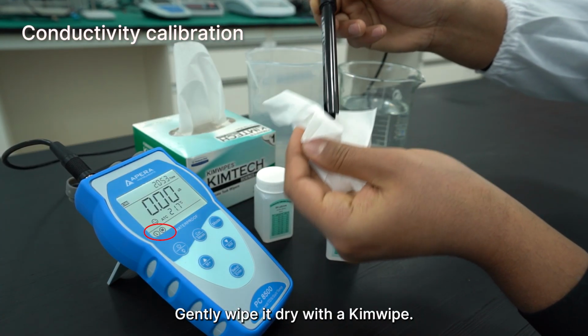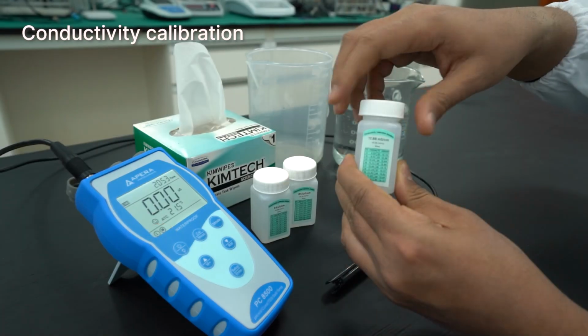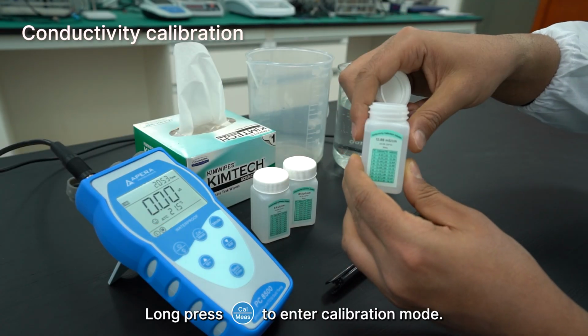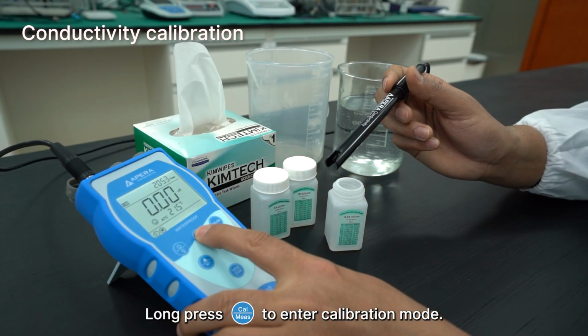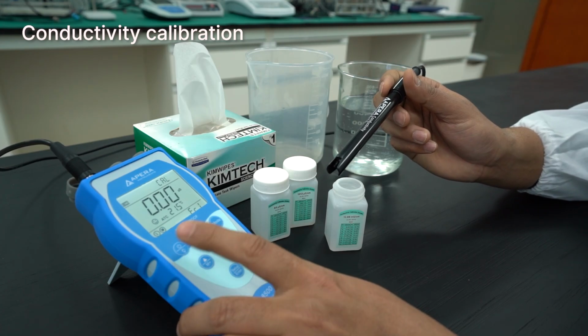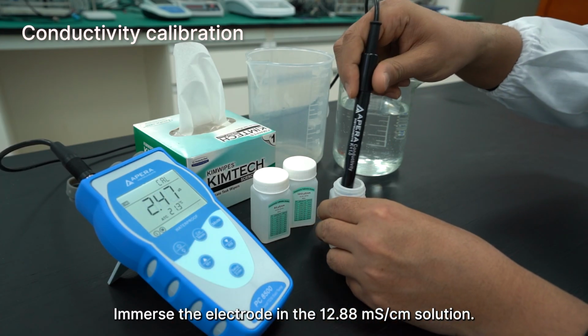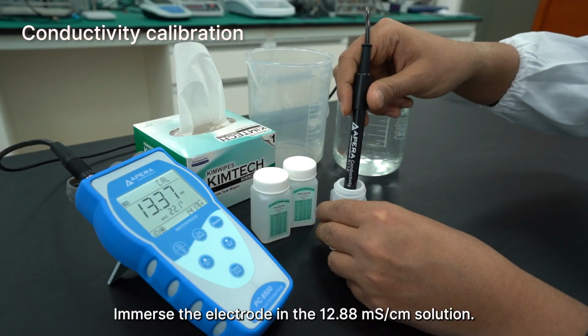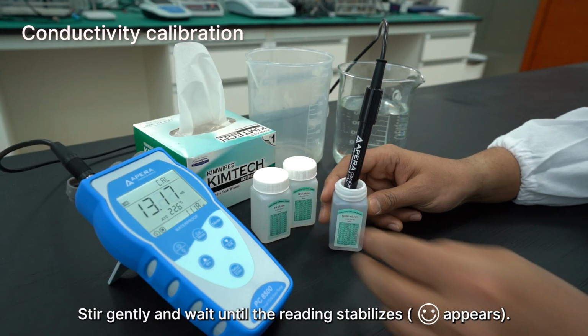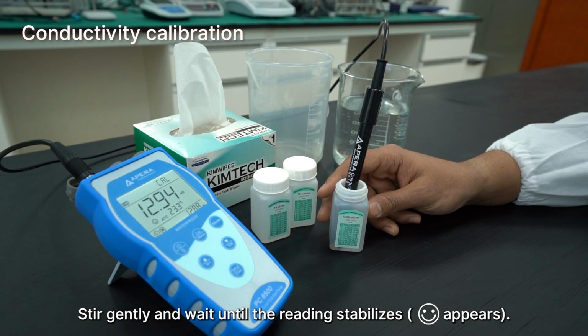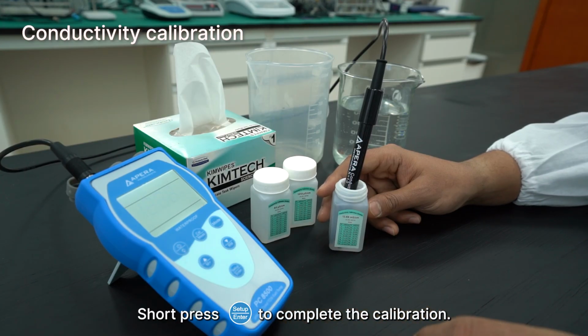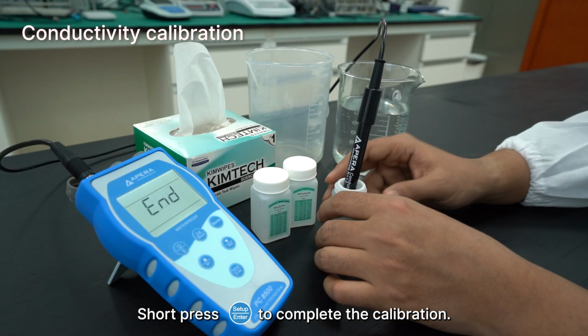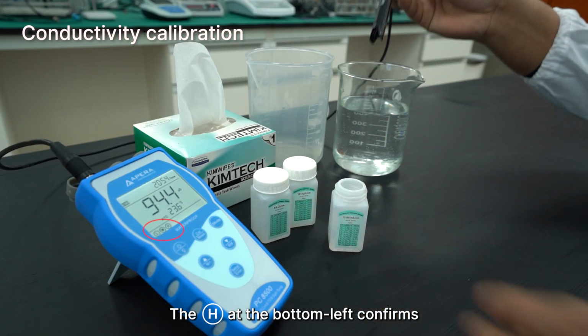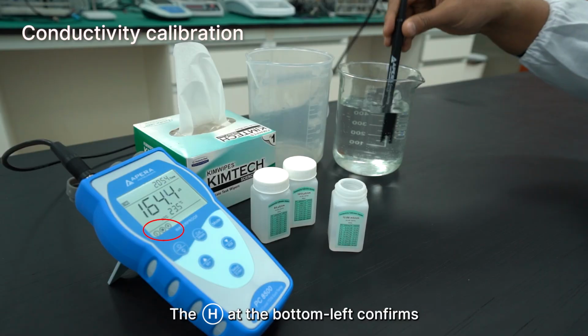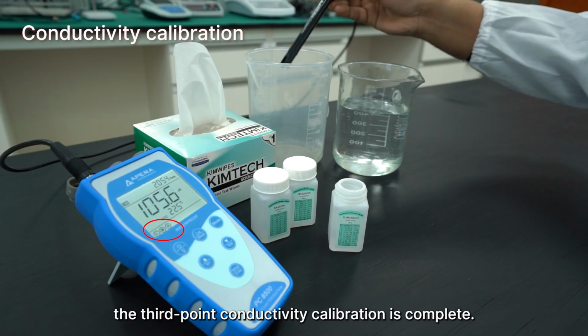Gently wipe it dry with a Kim wipe. Long press the cal button to enter calibration mode. Immerse the electrode in the 12.88 millisiemens per centimeter solution. Stir gently and wait until the reading stabilizes. Short press enter to complete the calibration. The H icon at the bottom left confirms the third point conductivity calibration is complete.